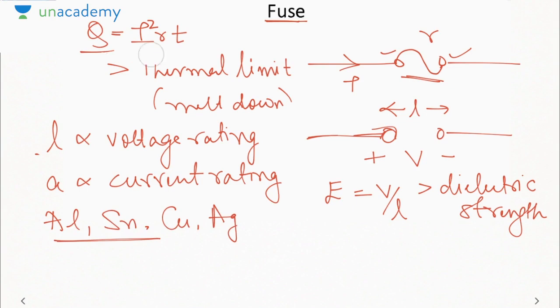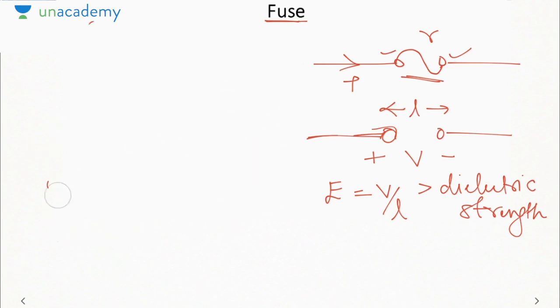Now as I told you, fuse meltdown is not too much desirable because the damage is permanent. Hence it is used as a backup protection. Now what is meant by backup protection? In any sport like football, cricket or any sport, we have some substitute players. Whenever any player gets injured, we have to replace that player with another player so that the game can continue. Similarly, in a protection system, if your protection system gets damaged, then how will you protect the power system? I am telling you that the protection system itself gets damaged, not the power system. So mind it, if the protection system gets damaged, then the power system will be unprotected. So we need to have a backup protection in place so that even if the protection system fails to protect the system, the other protection can work and protect my power system. Okay. So that is called backup protection.